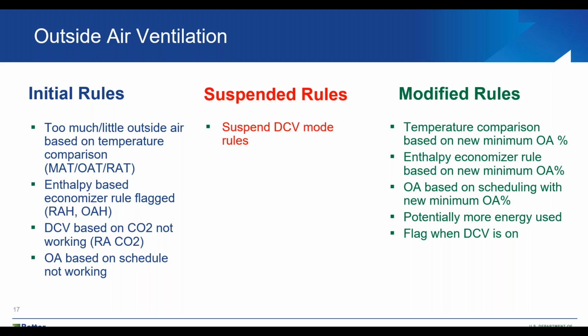So what happens as a result of COVID? The initial rules talked about comparisons of outside air temperature, mixed air, and return air, enthalpy comparisons, DCV, outside air based on scheduling. So one of the rules that has to be suspended now is going to be the DCV mode. If you don't suspend it, it's going to do the opposite of what you expect. You don't actually want it operating under COVID conditions. But you also need to modify and add a rule or a flag when DCV is now on. So the old one needs to be shut off temporarily, and a new one needs to be created for when it's on, because you don't want it operating for safety reasons. So instead of looking at the energy, you're looking at the safety reasons.